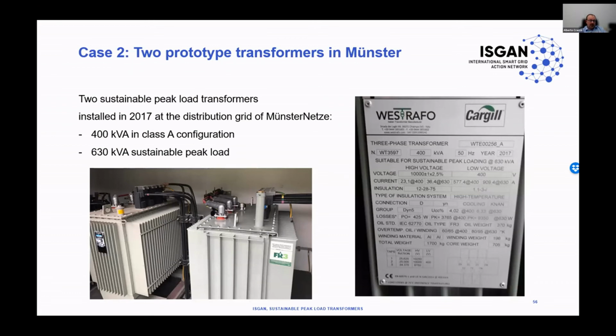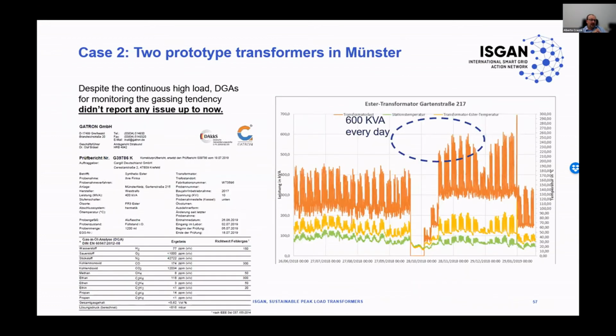Here we push to the extreme the concept of the SPL, and we had an overload of 55% compared with the nominal power. This was a test that the utility wanted to perform, and we can see in the next slide that the utility is using this transformer at a sustainable peak load during the lifetime of the transformer. As we can see in the diagram, during 1 year in 2018, we have a continuous load during the day of 600 kVA, compared with the 400 kVA nominal power of the transformer.